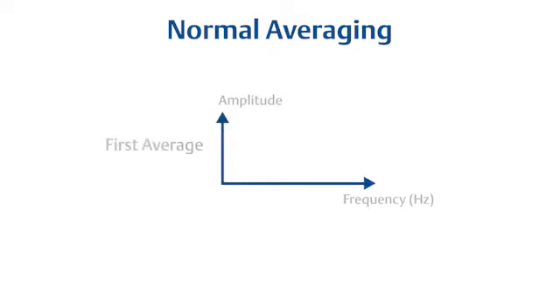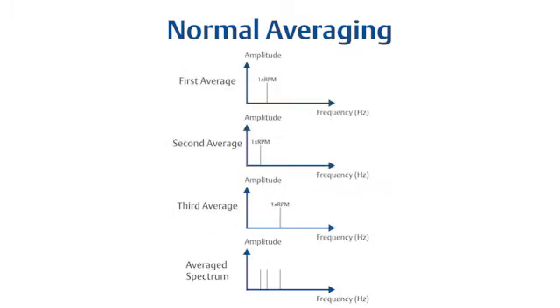Before we begin, let's review order tracking. Normally, vibration data is collected using spectrum averaging, which means that waveform data coming into the analyzer is used to calculate a spectrum. But the final spectrum created is actually an average of many spectra. This gives a good representation of the data and eliminates any random or one-time vibration sources. This does not, however, take into consideration variable speed.